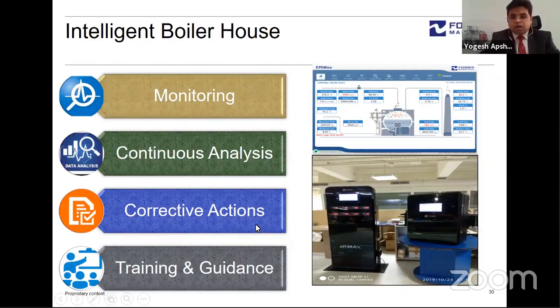Then corrective actions. We also do the corrective actions based on the data analysis. This is all digital. There is no human intervention. All the data loggers are giving the data to the monitoring system. The monitoring system is giving the signals to the analysis system, and then it takes the corrective action. Like if the O2 is increased, then it gives the alarms and the indications that you have to fine tune the steam to fuel ratio, or the fuel to air ratio, the damper position, or the burner tuning is needed, or the temperature transmitters are not operating. It gives a signal, and also it gives the training and the guidance.